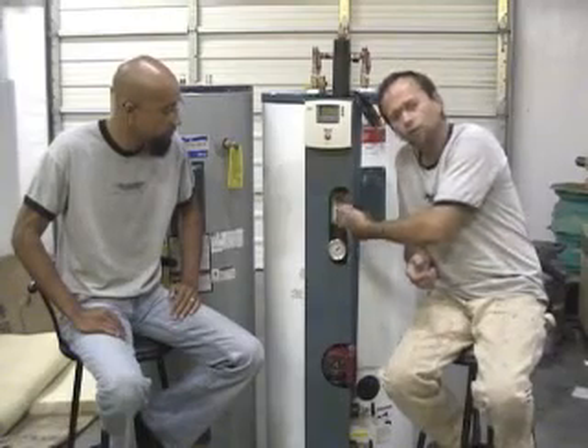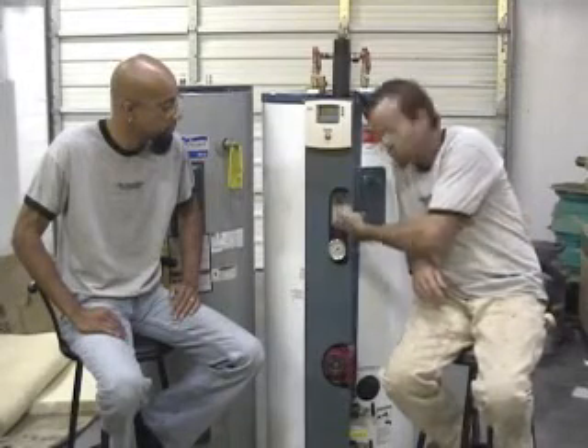Another feature is they have a built-in flow meter — something Heliodyne didn't tell us about. I think it's important. One reason is you can actually see the fluid in here to see when the fluid needs to be changed. Three to five years is really what's recommended, but you can see when the color changes and becomes a brown color — you should really change it.